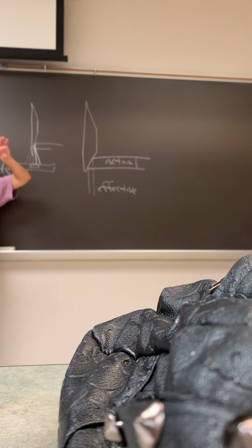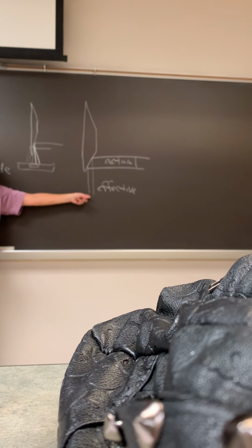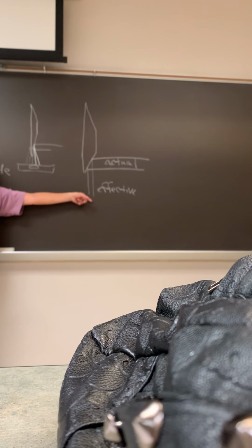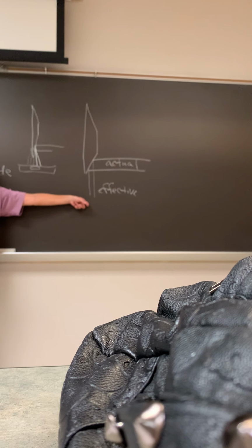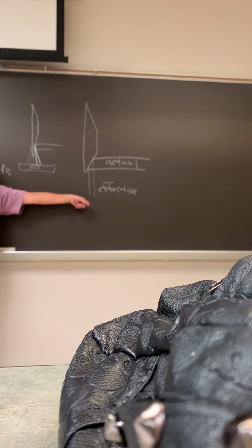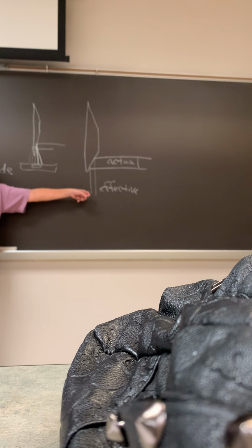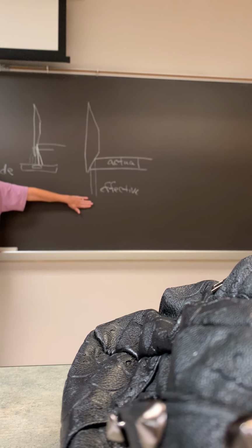So it's a large area of electron interaction, which is good because it dissipates heat because of that line focus principle. But because of the angle, we get a small effective focal spot, which is good for what? It's on your little chart. What is a small effective focal spot good for? Small, like small things. Good. Yeah, small things. So you want better spatial resolution. Okay, so a small effective focal spot is good for better spatial resolution.